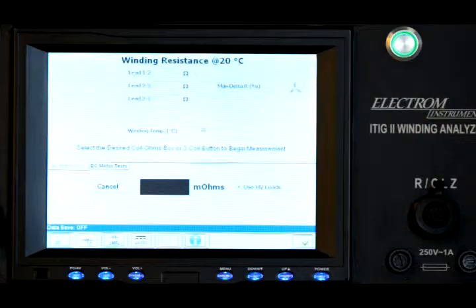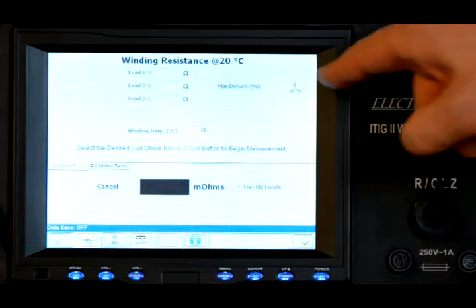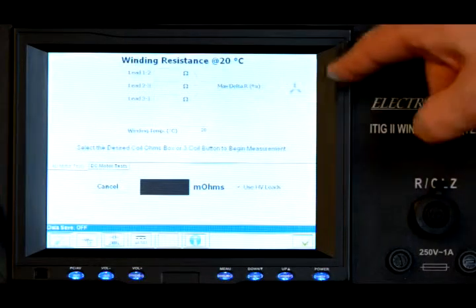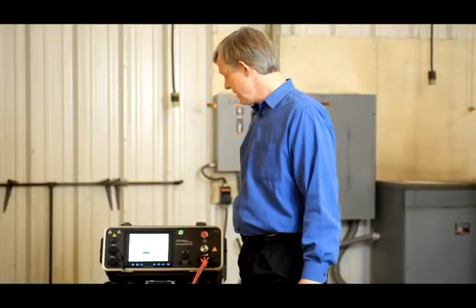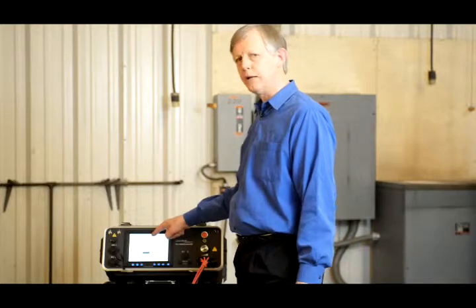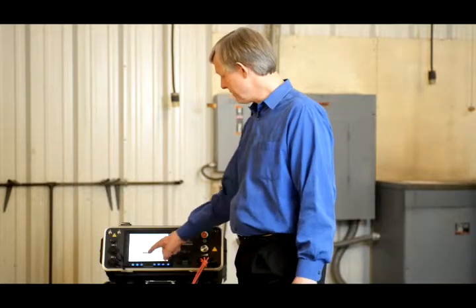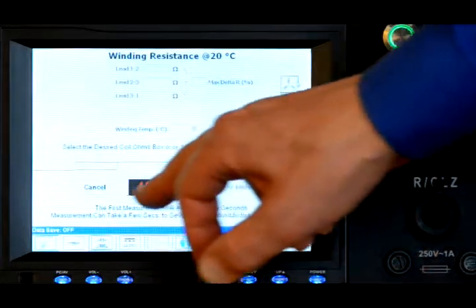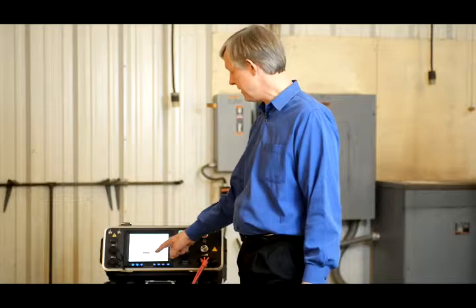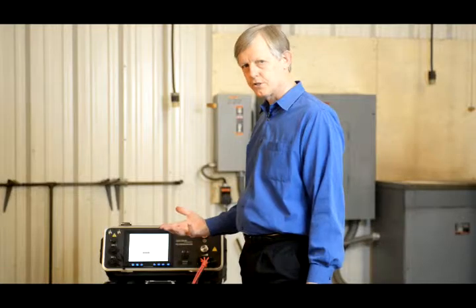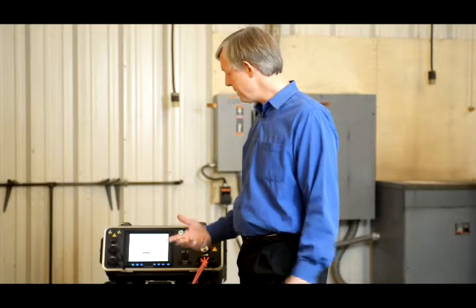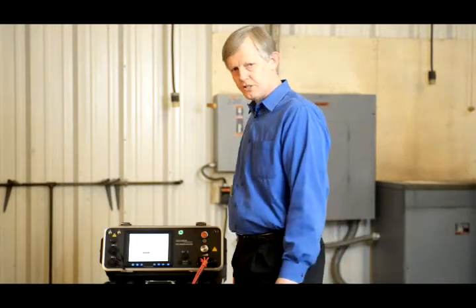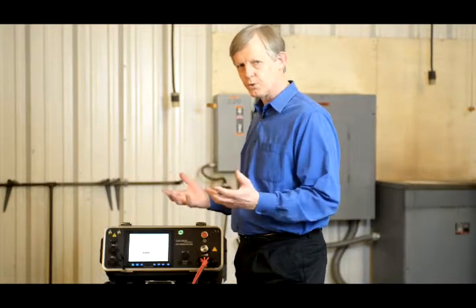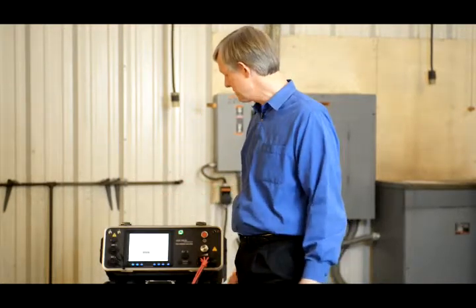To start the test, you can click in the fields here. Do one at a time, but we're going to do them all automatically in the sequence by pressing this button, the little triangle button in the corner. The little field turns green when it is active, and pretty soon a measurement appears at the field down here. It takes a little while for it to stabilize, and depending on the resistance in the windings, that can take a few seconds or it can take up to 3 minutes.